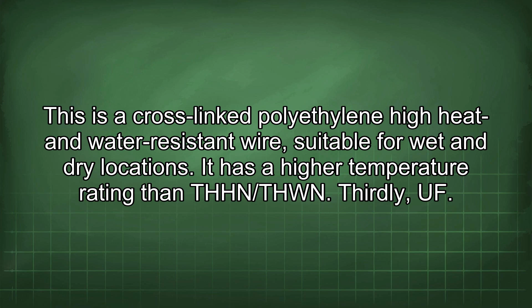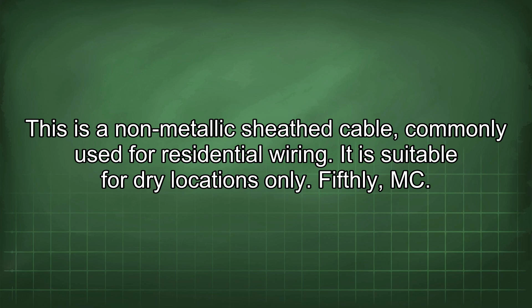It has a higher temperature rating than THHN/THWN. Thirdly, UF. This is an underground feeder cable, designed for direct burial in the earth. It is moisture-resistant and sunlight-resistant. Fourthly, NM-B. This is a non-metallic sheathed cable, commonly used for residential wiring. It is suitable for dry locations only. Fifthly, MC. This is a metal-clad cable, consisting of insulated conductors enclosed in a metallic sheath. It is suitable for dry and damp locations and provides excellent protection against physical damage.